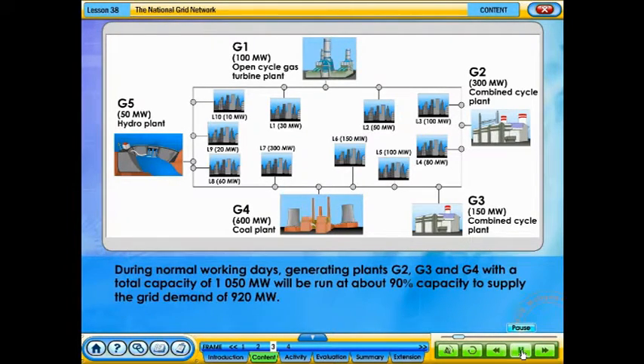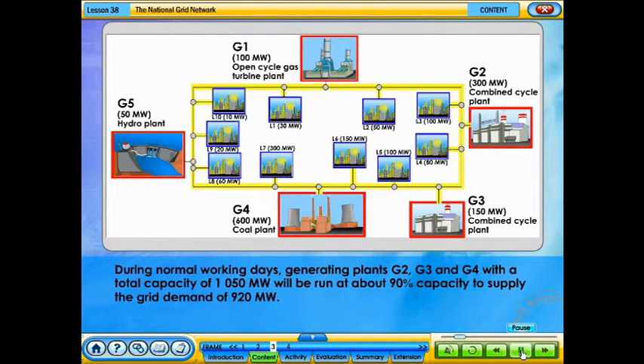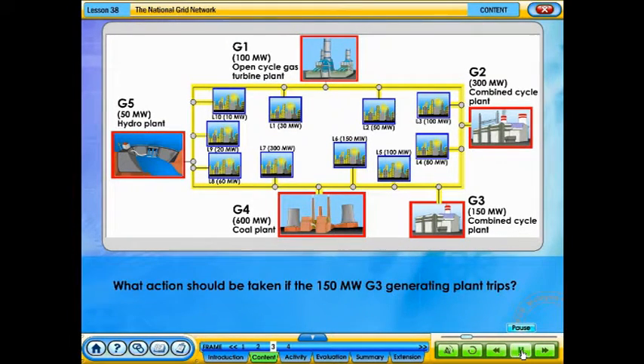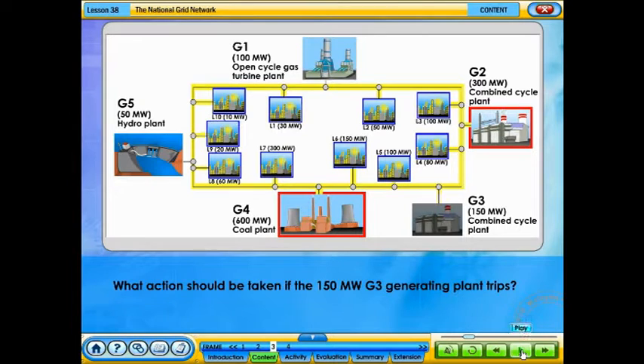During normal working days, generating plants G2, G3 and G4 with a total capacity of 1,050 megawatts will be run at about 90% capacity to supply the grid demand of 920 megawatts. What action should be taken if the 150 megawatts G3 generating plant trips?